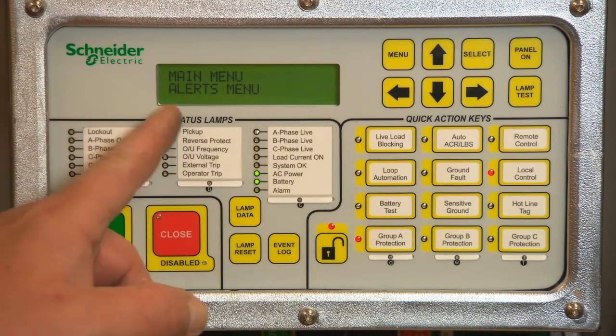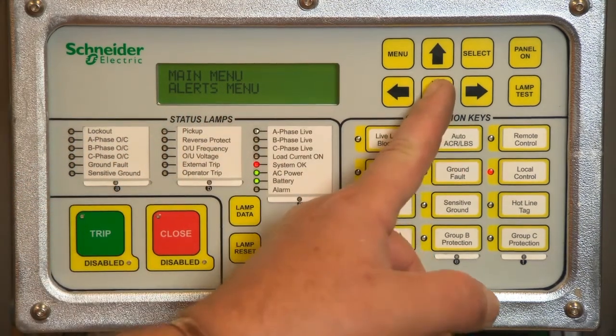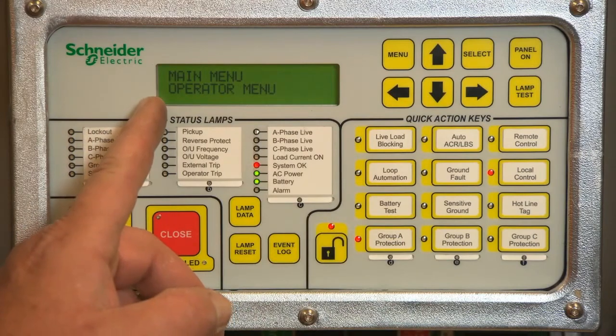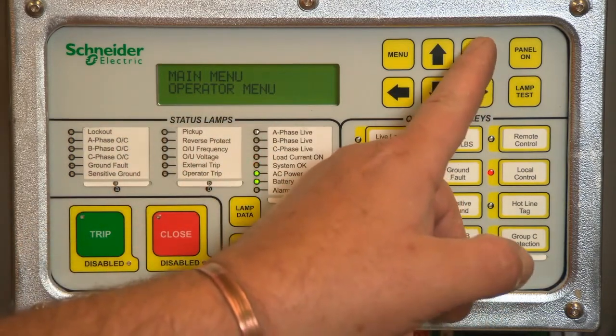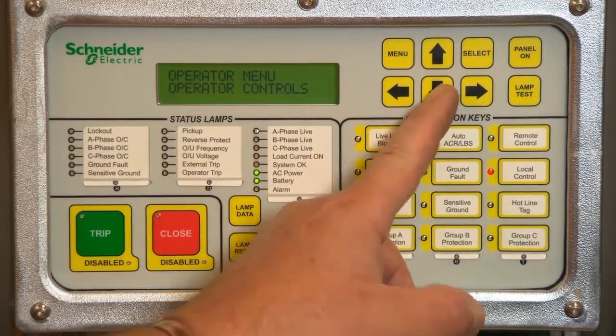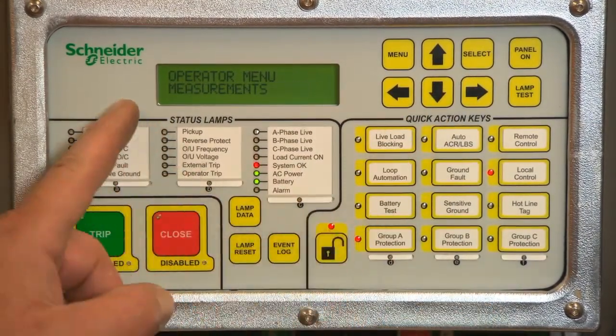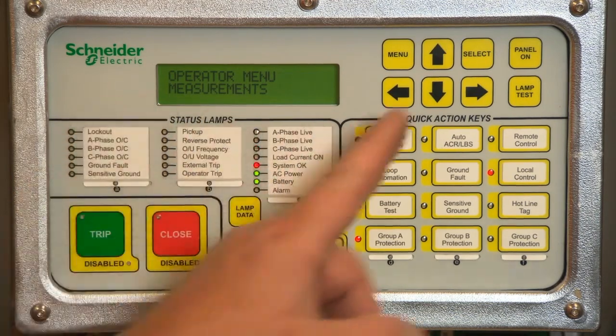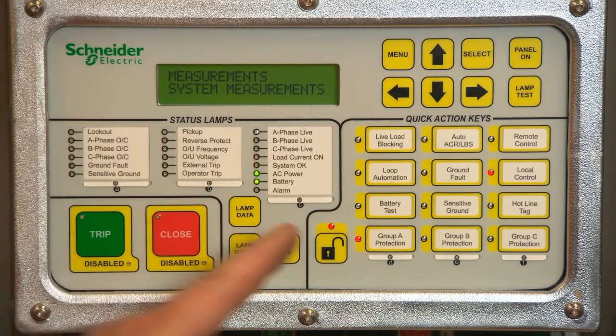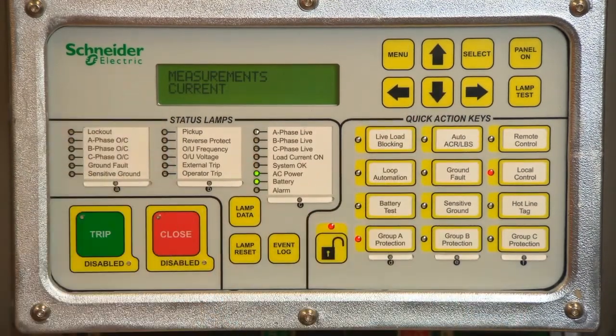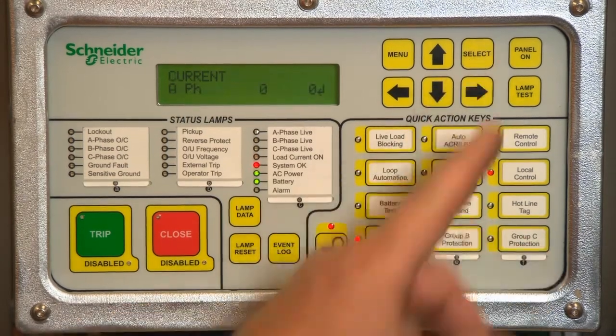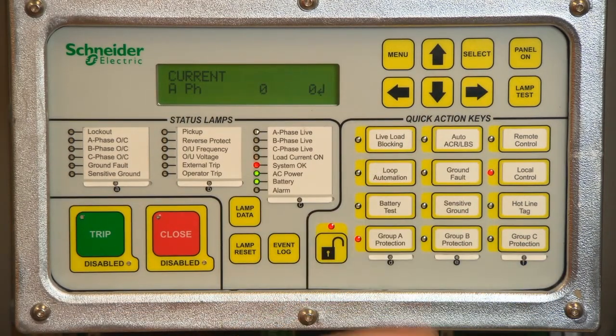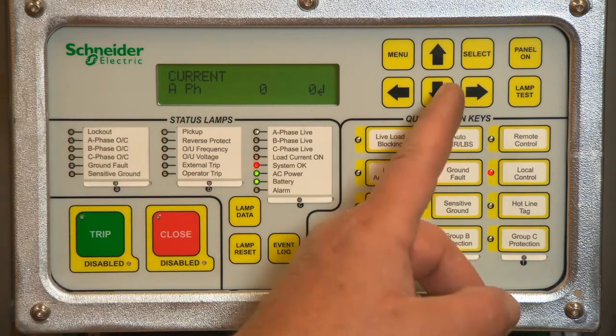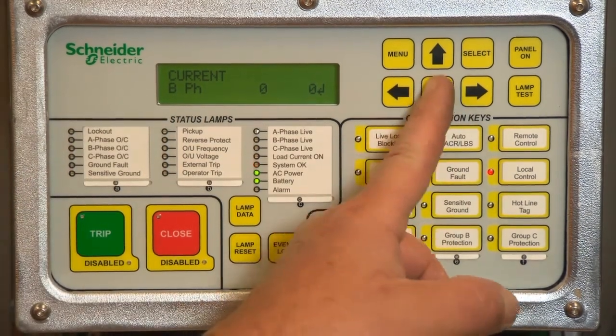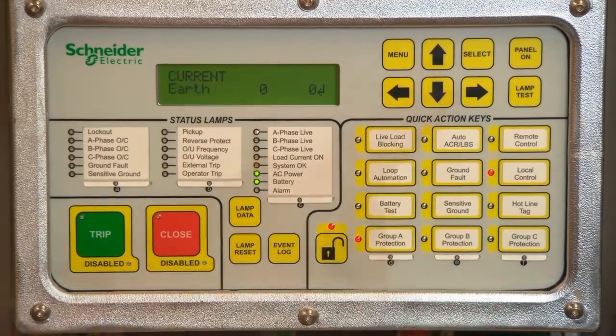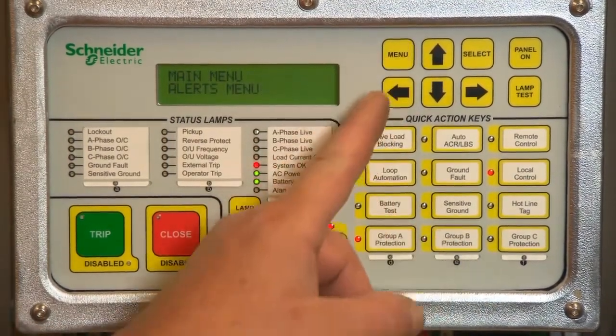Scrolling menu display. To access the current display from the main default display, press the down arrow to reach Operator menu. Press Select. Scroll down to reach Measurements. Press Select. This will display System Measurements. Scroll down again to display Current. Press Select. You are now able to scroll through A phase current, B phase current, C phase current, and ground or neutral. Press Menu to return to the main display screen.